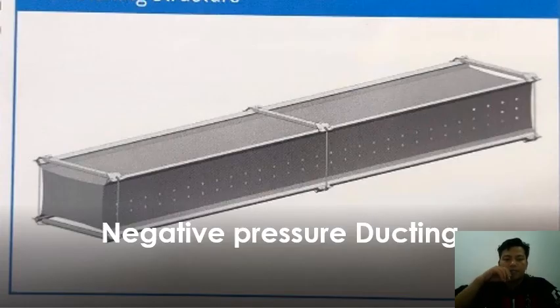The second one is negative pressure ducting. We supply only square and triangular shapes of fabric ducting. The fabric is essential for extract ducting. We tension the wall using a combination of suspension profile, tensioning bolt and threaded bar. Air is drawn into the duct through perforations that can be positioned on any side and anywhere along the length of the duct.